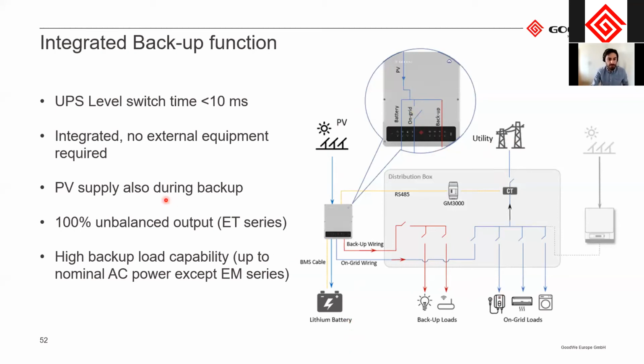It's also possible to achieve unbalanced output of the ET series. So when you have a three-phase inverter, you can have different loads connected to the different phases, and you can also control the power export function here so that you don't export more than your set value per phase as well.